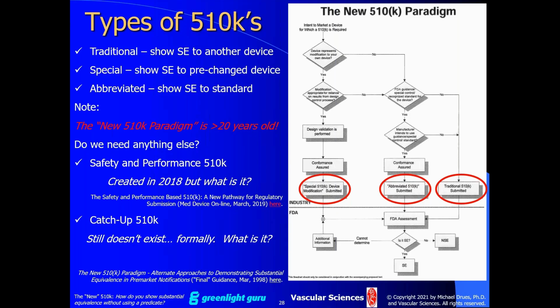And I don't want to talk about this in too much detail because it's a different topic, but really we have no way to notify FDA of a series of changes that we may have made to an existing medical device that all individually have been handled under a letter to file. And the reason why this is so problematic is because some of you are familiar with the phrase predicate creep, which is the Achilles heel of the 510K.